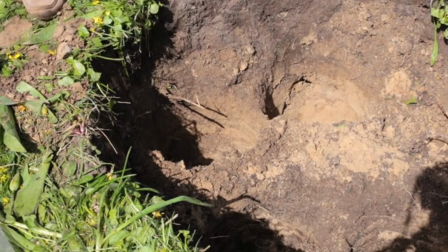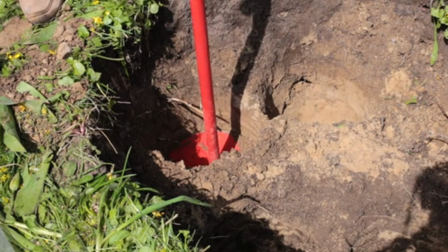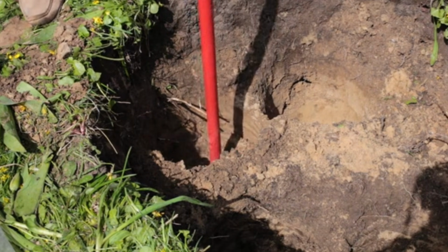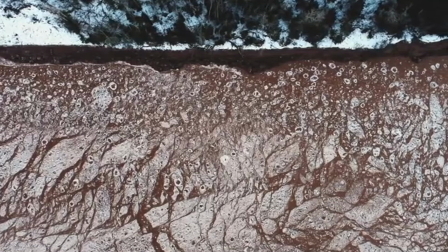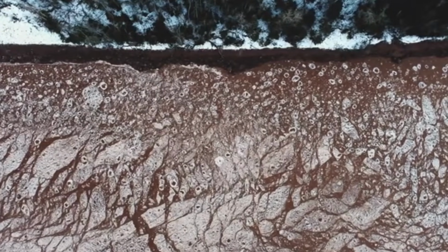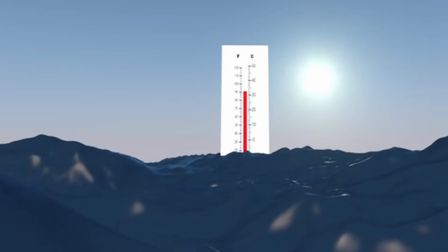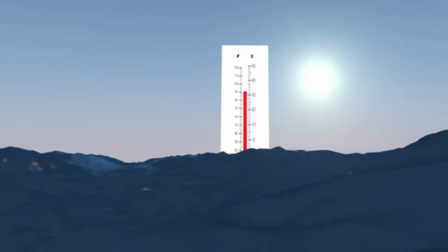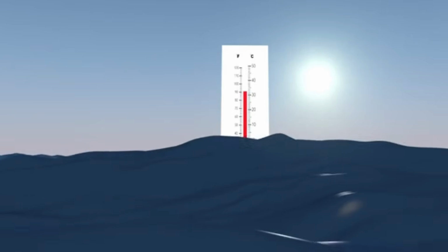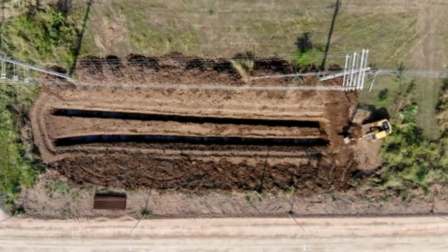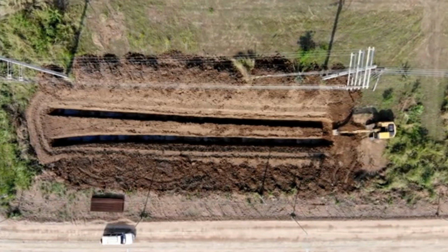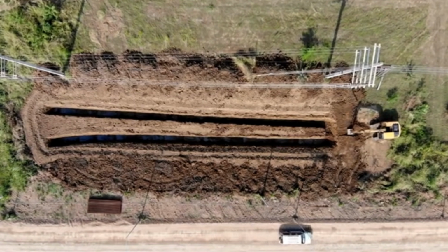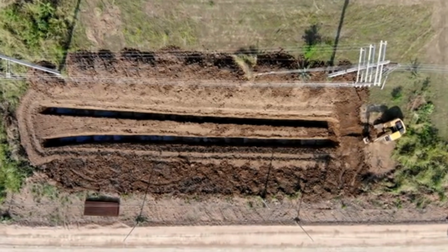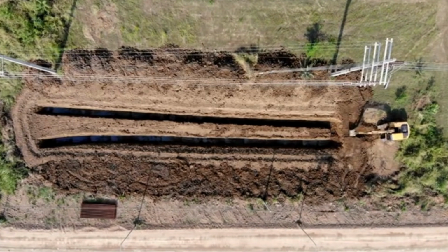That's your loop. The trench should be dug to a minimum depth of 4 feet in northern climates and 3 ft in southern climates. 4 feet is the magic number because frost rarely penetrates below 36 inches, even in the upper Midwest. And at 4 ft, the soil temperature variation between summer and winter is less than 6 degrees in most regions. If you can dig to 6 ft, even better. The temperature stabilizes further and your cooling capacity increases by about 15%. The trench layout should be a serpentine pattern back and forth across a section of your yard about 20 ft by 30 ft, with the hose loop spaced 2 ft apart to prevent thermal interference between adjacent runs.